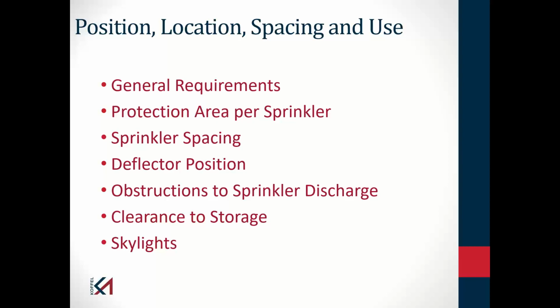There is language in newer editions of NFPA 13 that does say you do not have to wet 100% of the area. I could have a small corner of a room that I don't quite have adequate coverage. If we have a fire in that corner, it's not going anywhere. We're still going to control that fire because we're wetting everything around that space. So unless you have a keen interest in trying to quickly suppress the fire in what's in the corner of that room, it really should not be a problem.